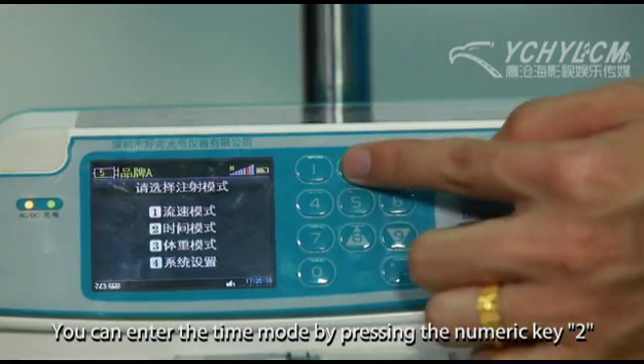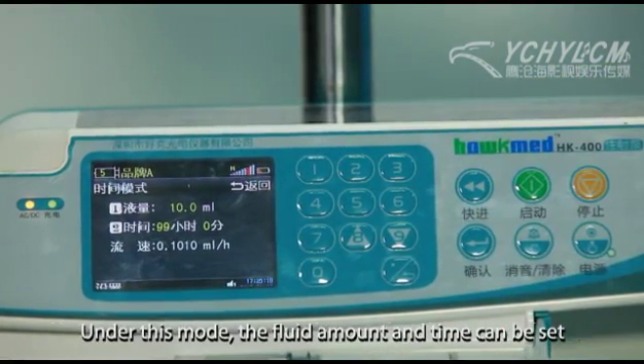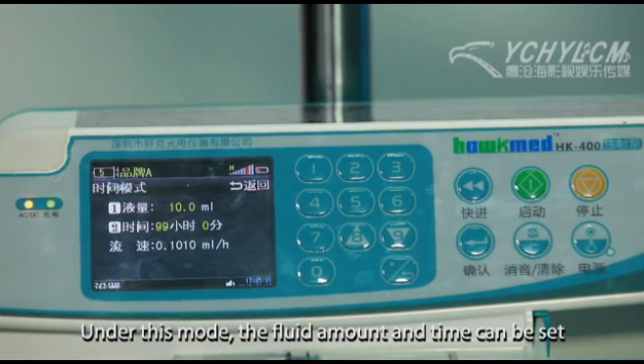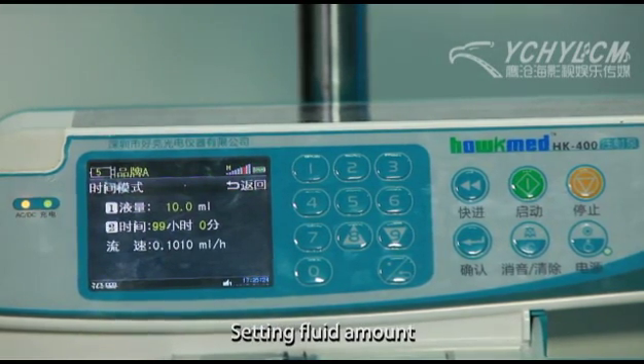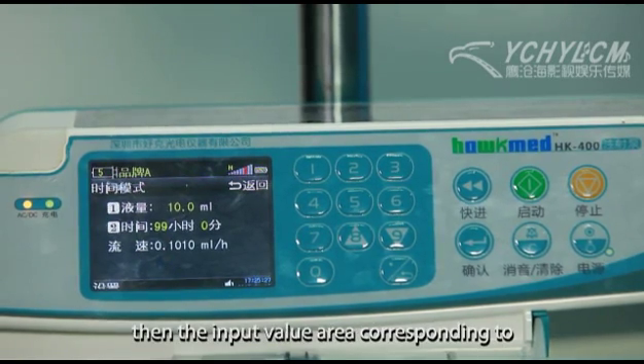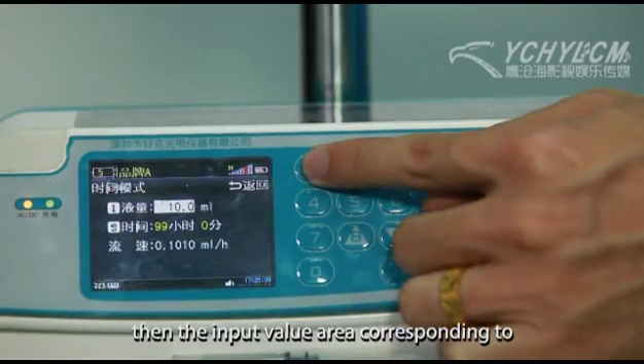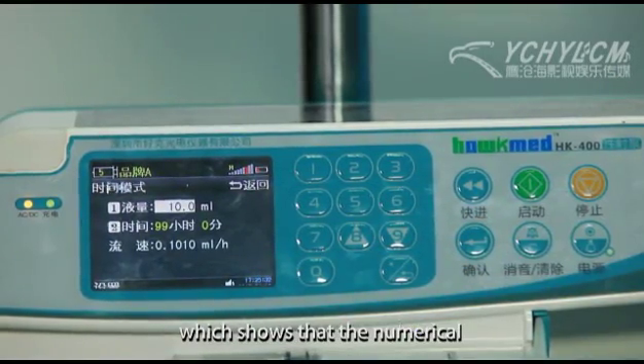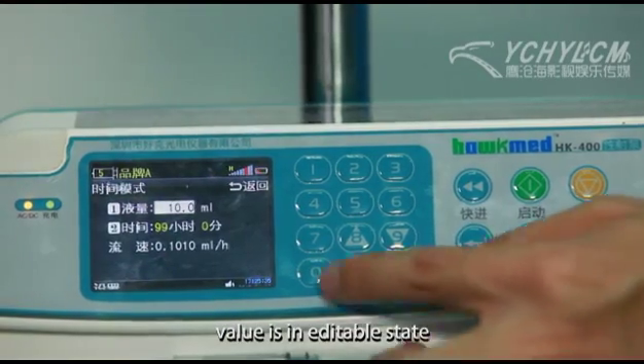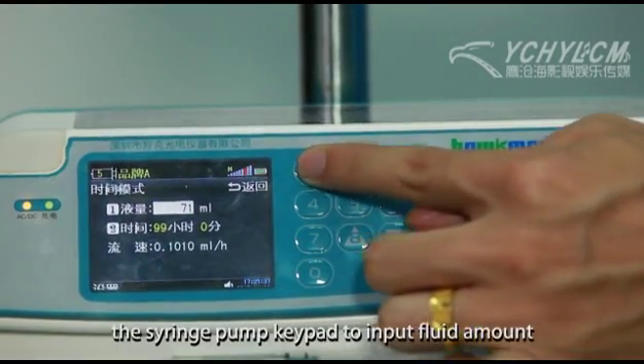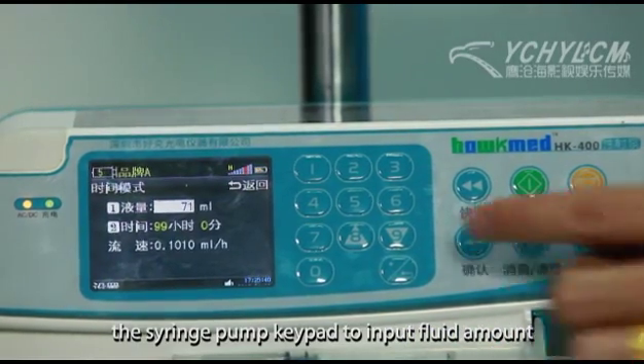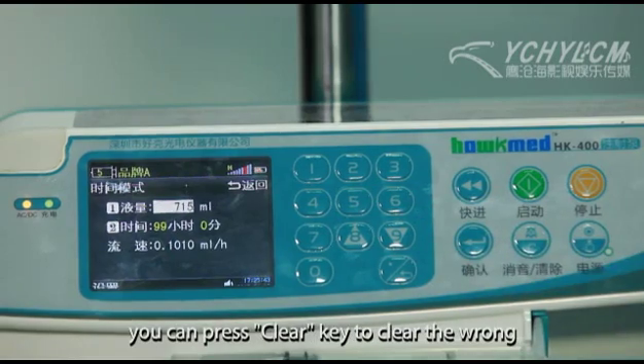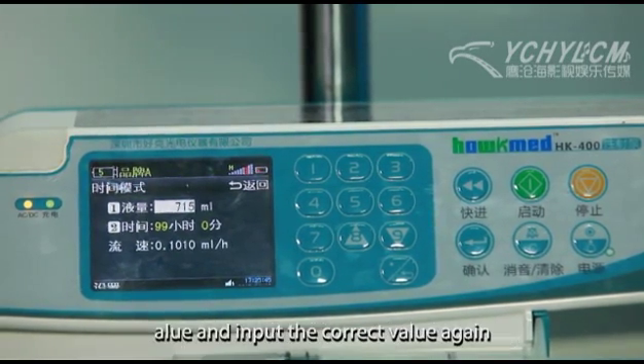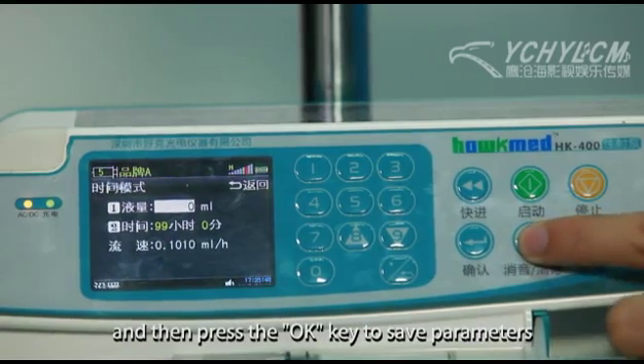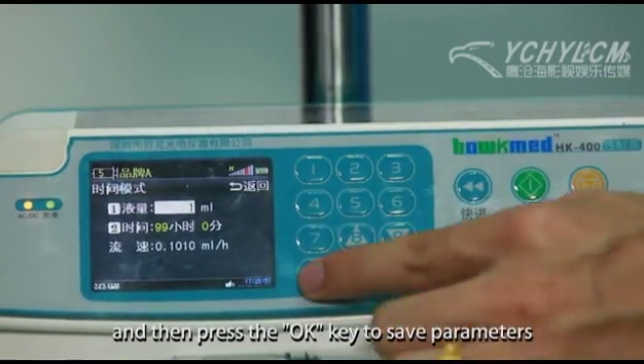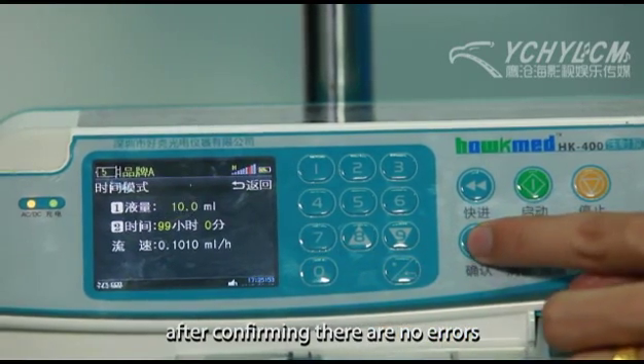You can enter the time mode by pressing the numeric key 2. Under this mode, the fluid amount and time can be set. Setting fluid amount. Press the numeric key 1, then the input value area corresponding to the fluid amount has a shadow, which shows that the numerical value is in editable state. Press the corresponding number on the syringe pump keypad to input the fluid amount. In case of input error, you can press the Clear key to clear the wrong value and input the correct value, and then press the OK key to save parameters after confirming there are no errors.